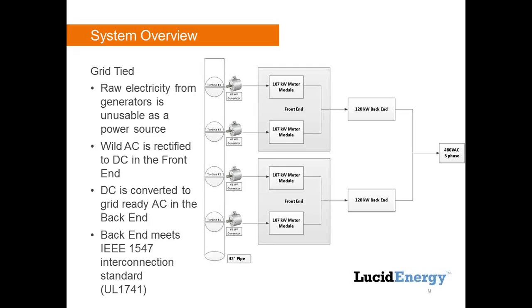Our system has a fail-safe where when the grid goes down, in a quarter of a second our turbines stop. We did live testing for our power utility PGE — one requirement was a grid loss test, simulating the grid going down by throwing the big breaker at the street. With our lift-based turbine operating at about 250 RPM, in an eighth of a second the turbine ramps up from 250 to 500 RPM — it doubles the speed and just wants to take off, creating a lot of stress on components. So we brake it in a quarter of a second — the system slams to a stop using an essentially large truck disc brake system, ensuring no power is put onto a down grid.